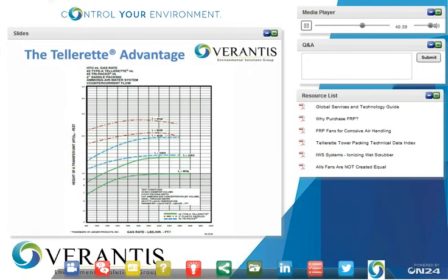So this is a comparative curve. I know it's a little bit hard to read. It's the height of a transfer unit versus gas rate for scrubbing SO2 from an airstream using caustic solution. And the green, blue, and red are comparative curves, green being the Tellerette packing, blue being the tri-pack, and the red being the saddle packing. HTU is the height of a transfer unit, and in this case, the lower the number, the better. And what you can see here is that the Tellerette packing actually provides better performance than both the filament style tri-pack and much better than the extended surface packing.